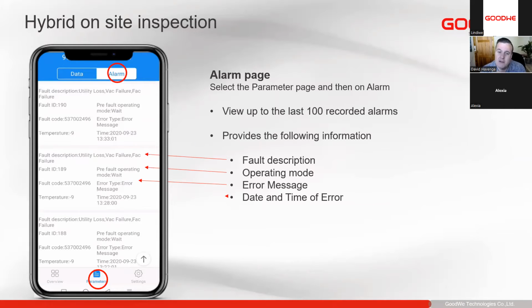Here you'll see the last 100 recorded alarms, be it a BMS alarm, an inverter alarm, all the alarms will be listed here. Sometimes there are alarms that might not appear here, especially if it's a sudden fault or sudden shutdown where the device hadn't had time to log the alarm, but very often we can see this on the back end. But for the most part, you'll see the alarms and it will tell you exactly what's going on. It'll tell you the fault description, what the fault could be, so utility loss, VAC, FAC failure, which means the grid went off in most instances. Which mode the inverter is in. The type of error: is it an error or is it a warning? And then the date and time of the error, as well as the fault code.